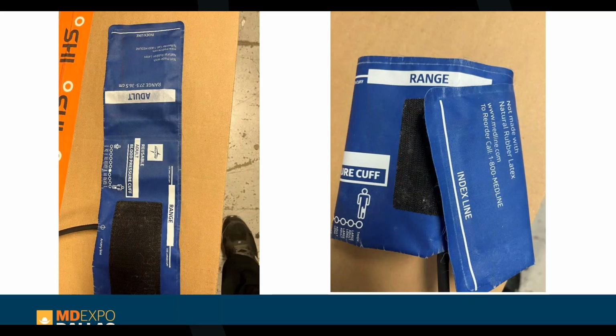That's my foot there, and this is a normal cuff. See this index line? This part should fold around like this. I've put it at an angle so you can see it, but that line should fall within this white range here, the wider part being better. One label says use a larger cuff, the other says use a smaller cuff. If the line falls in that white range, it's the right size cuff. If it's outside that range, it's the wrong size and you need to go to a smaller or bigger cuff.